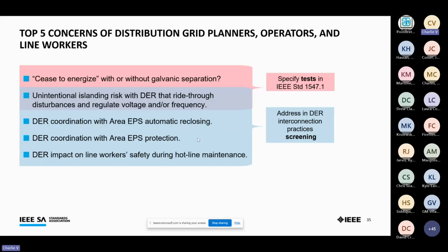So it's interesting to note that even after all the inclusion of the smart grid aspects, a lot of the main concerns still fall back to some of the fundamentals of 1547. And again, the backstop for 1547 remains that if the grid remains out of defined frequency and voltage limits, a DER must get off the system and stop energizing the power system until it measures that the frequency and voltages have returned and remained within the allowable range. Again, the default is a 5-minute monitoring period, but that monitoring period can be shortened. So I do want to emphasize that with all the addition of the smart grid bells and whistles and capabilities, that backstop remains: if there's a sustained grid issue, not just an outage, but if voltage or frequency are out of range, the DER must get off.